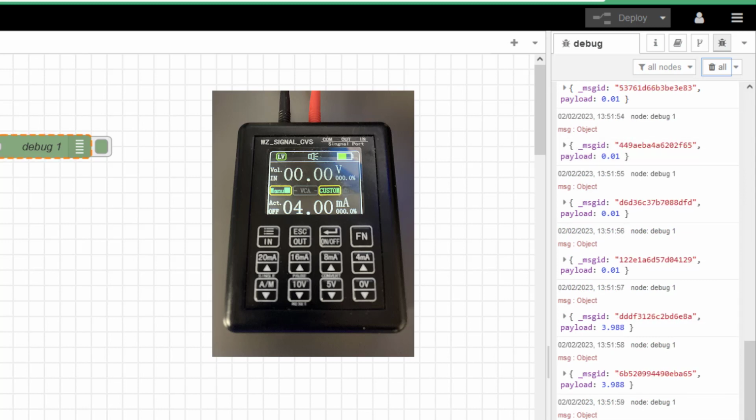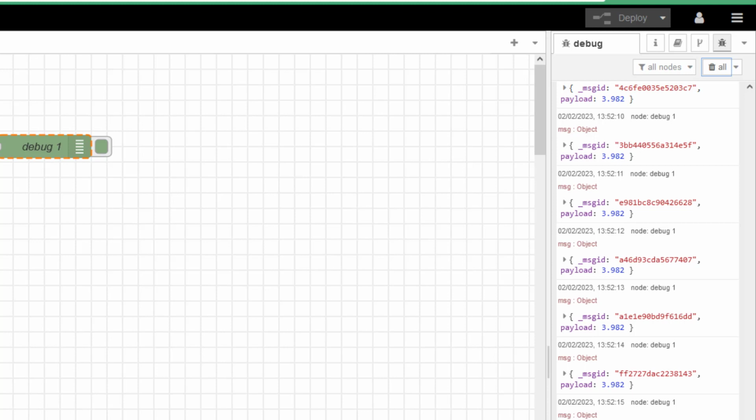So there's a little bit of calibration that needs to be done on this. But the problem is my milliamp source is very, very cheap, so I wouldn't really calibrate the card to this milliamp source. Now if I keep going up, I think I will go up a milliamp at a time, you should see these values scrolling up the screen, and the values are changing as I go up my meter. So I go all the way up to 20 milliamps. Now, there we go. So I need to scale that.